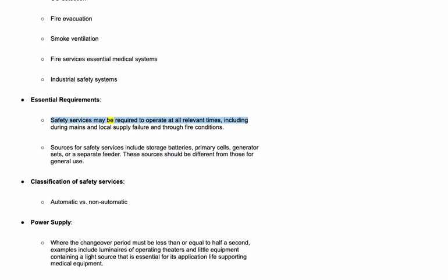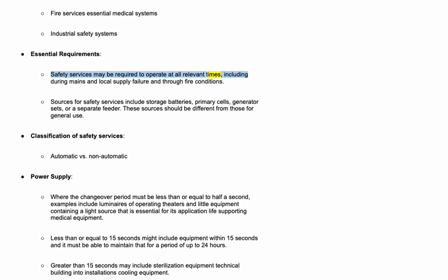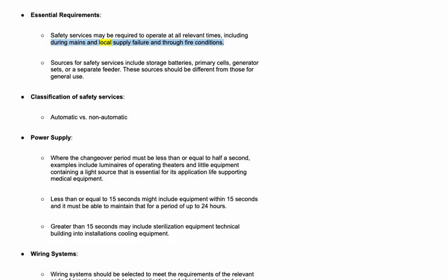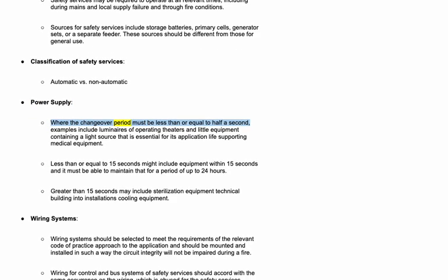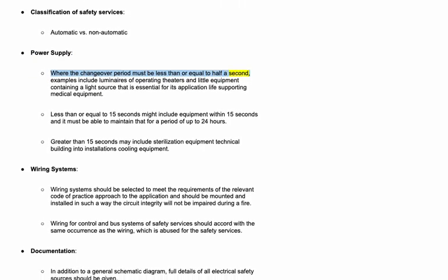Safety services may be required to operate at all relevant times, including during mains and local supply failure and through fire conditions. Sources for safety services include storage batteries, primary cells, generator sets, or a separate feeder. These sources should be different from those for general use. Classification of safety services: automatic versus non-automatic. Power supply, where the changeover period must be less than or equal to half a second.